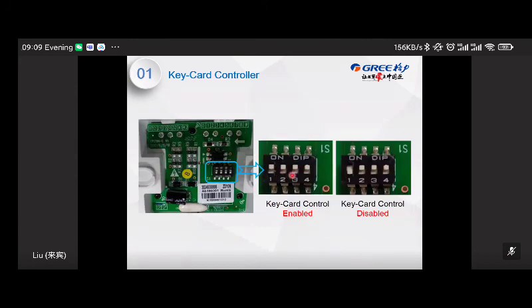However, for the XK79, maybe the customer doesn't want to use the keycard function, and the default setting is enable. Switch on, the first dip switch on means enable. However, if they don't want the keycard function, they can just switch off the first one to disable. Okay, that's the difference, right, between the hotel keycard controller and the ordinary wire controller.